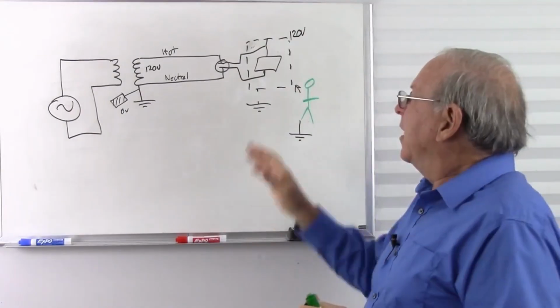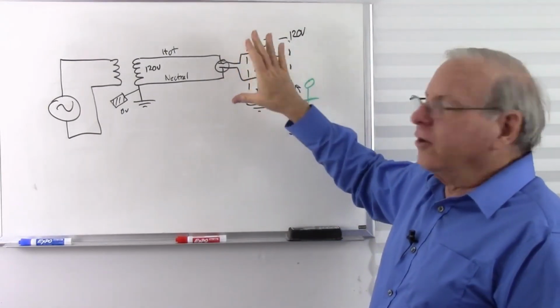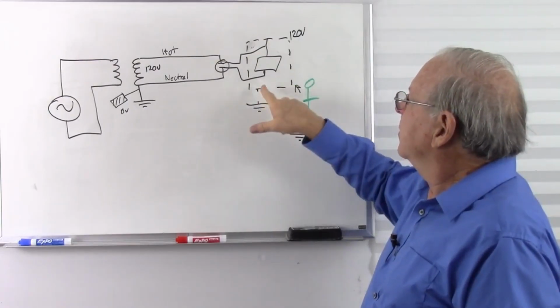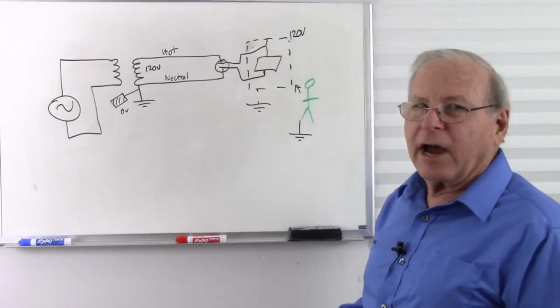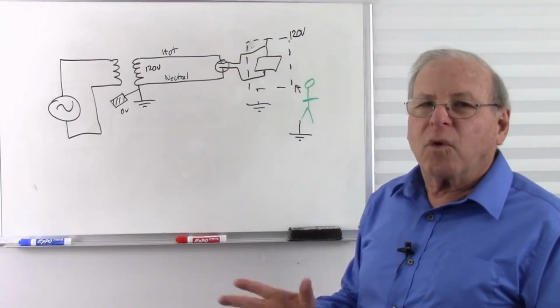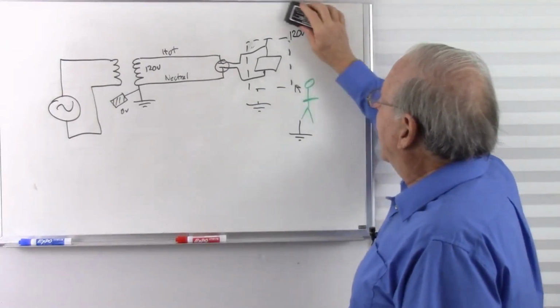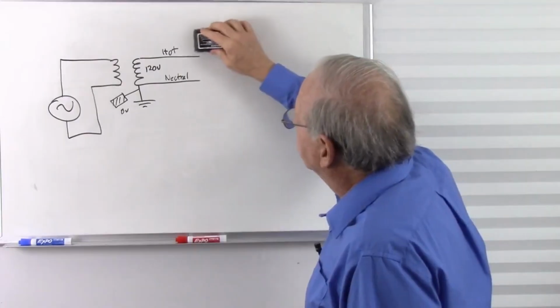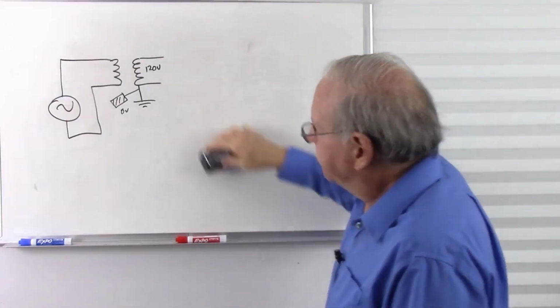So it's in the right direction, but if we have a double fault connection there and a loss of ground, I'm still in danger. So what can we do? What we can do is add an isolation transformer. Let me move this back a little to make some room here.